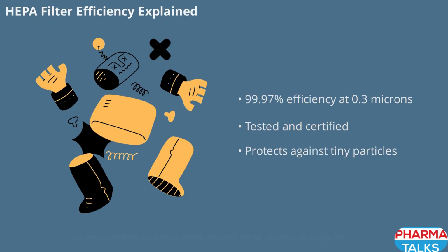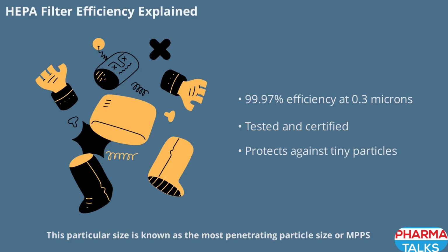HEPA filters are defined by their impressive efficiency. To be classified as a true HEPA filter, it must remove at least 99.97% of airborne particles that are 0.3 microns in size. This particular size is known as the most penetrating particle size, or MPPS, and serves as the benchmark for HEPA filter performance. The filters are rigorously tested and certified to ensure they meet these strict standards, providing reliable protection against even the smallest contaminants. This level of efficiency is why HEPA filters are trusted in environments where cleanliness is non-negotiable.